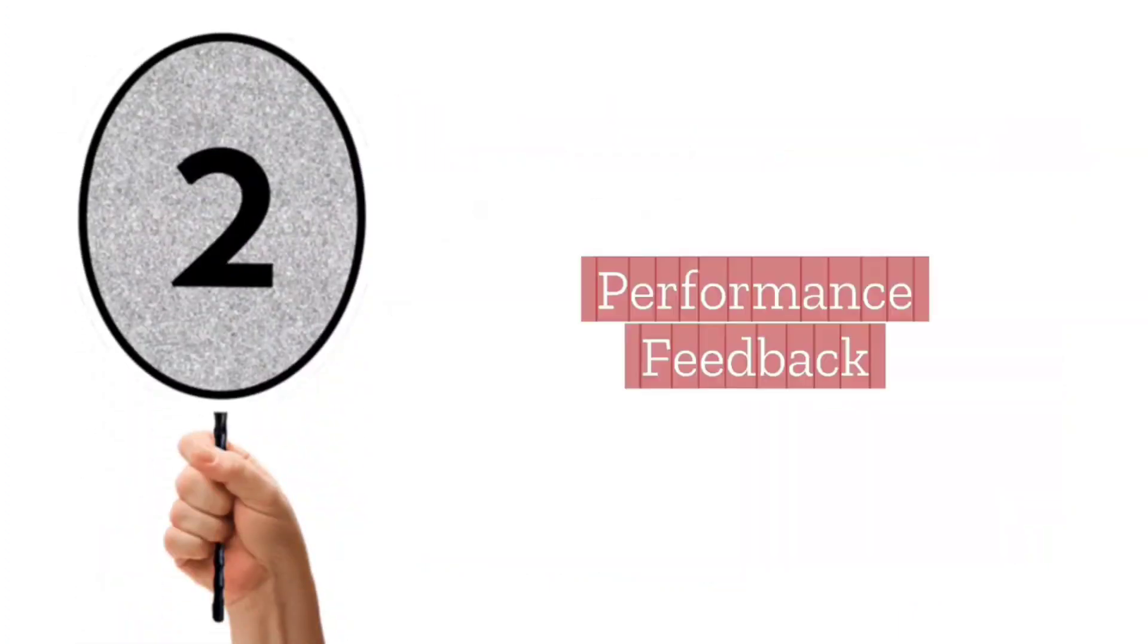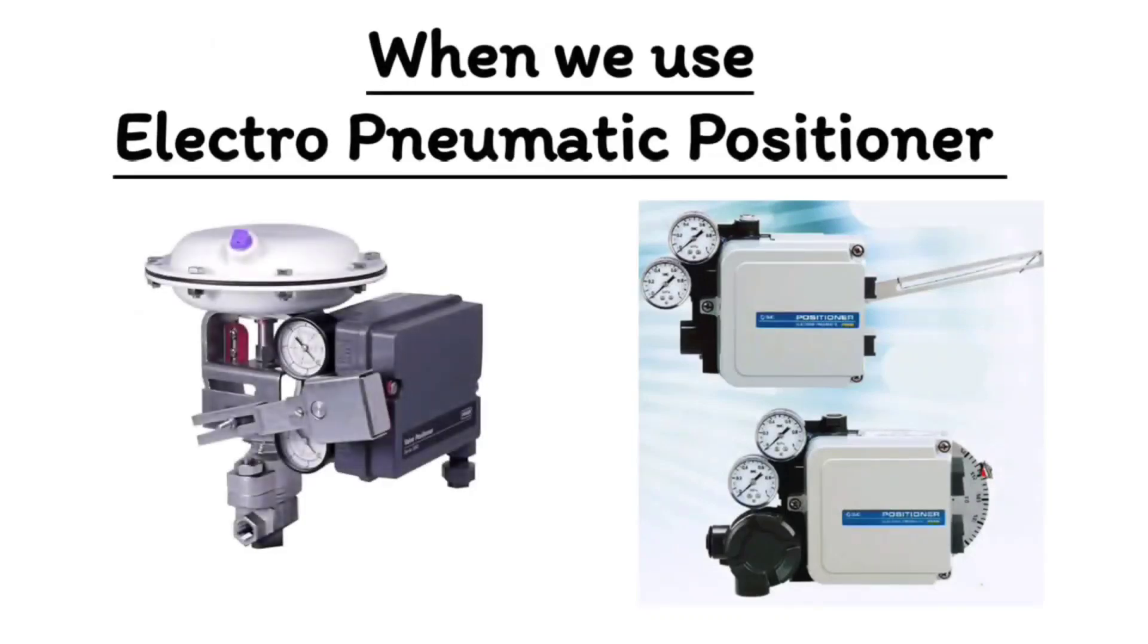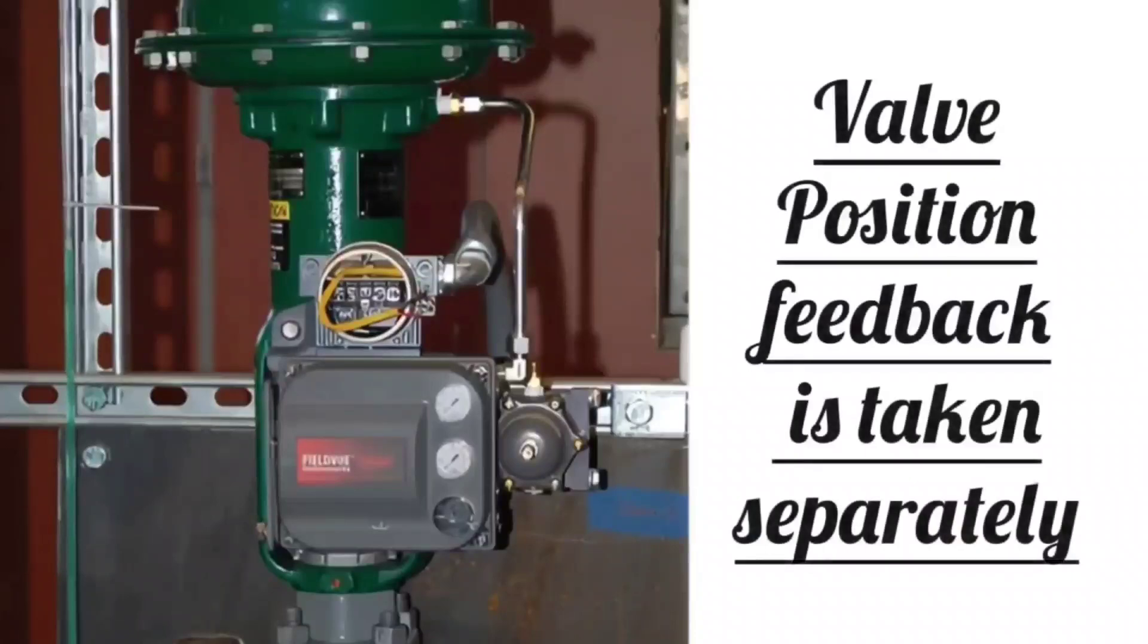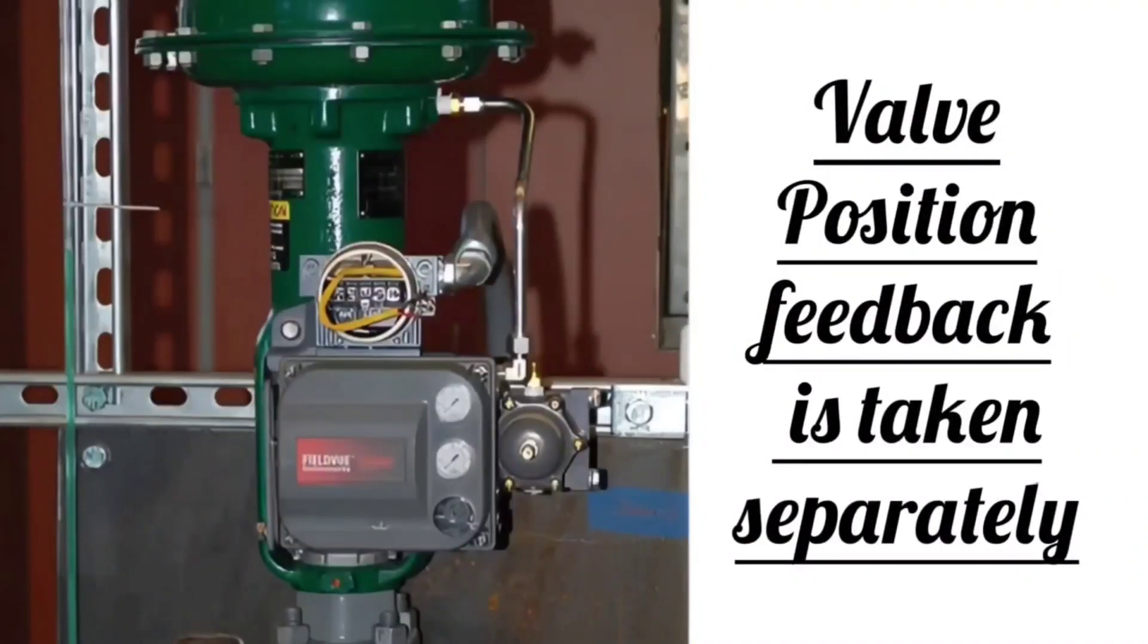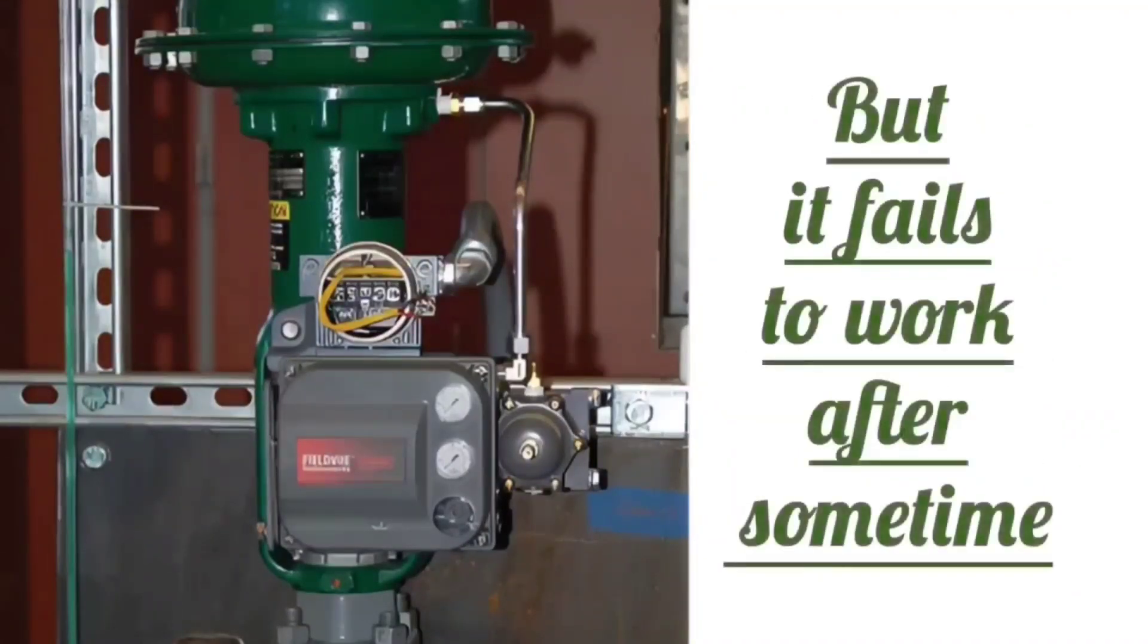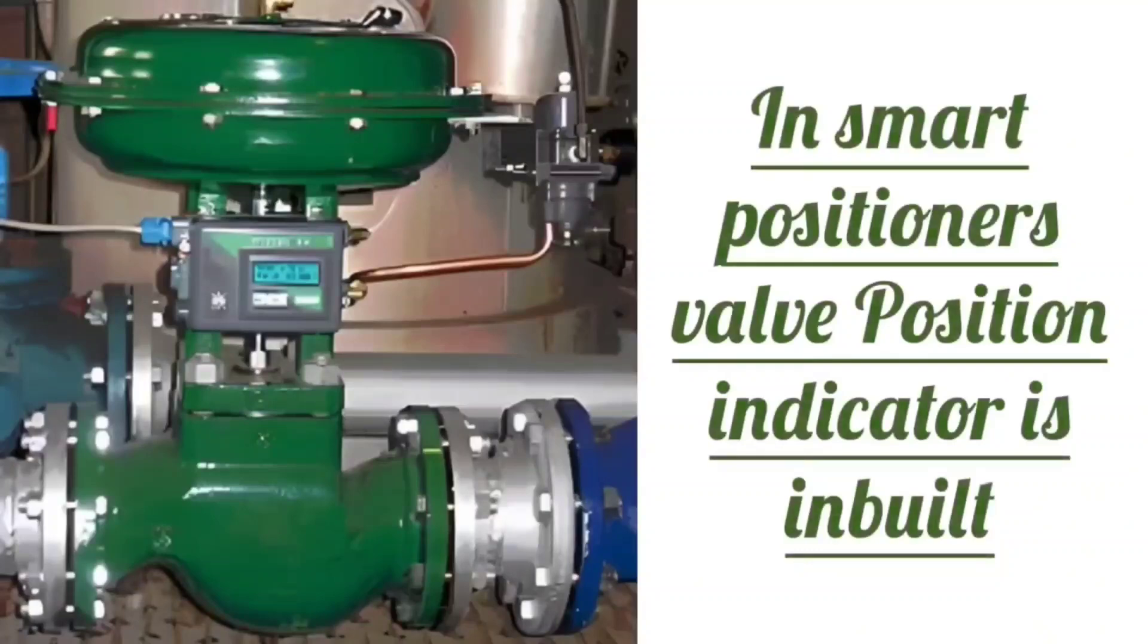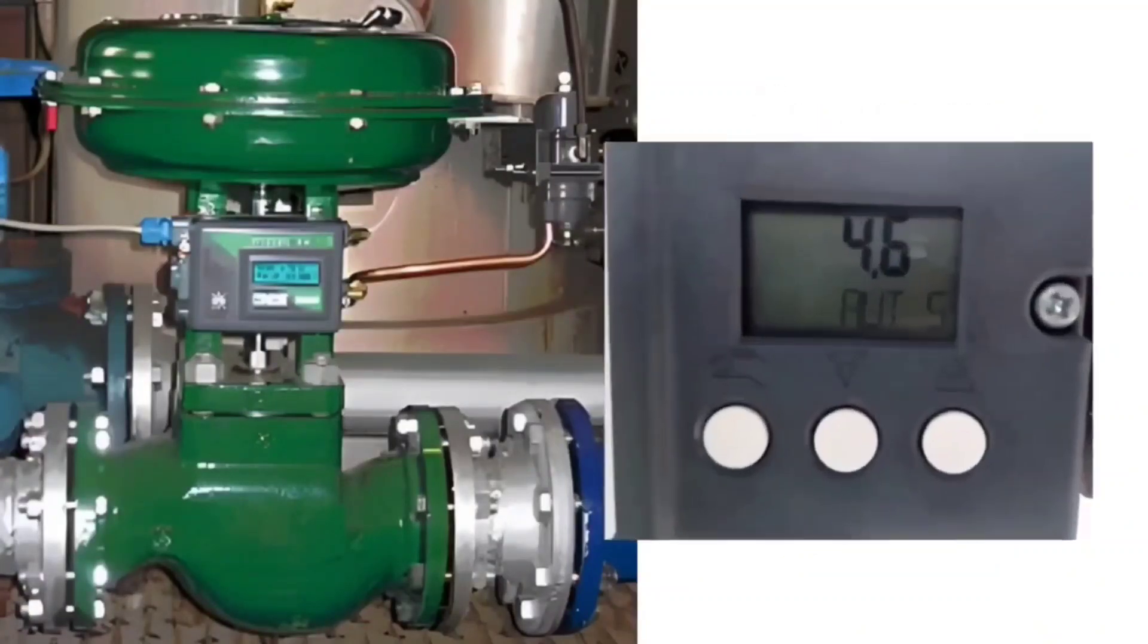Next is performance feedback. When we use normal electro-pneumatic positioner, the position feedback signal of valve has to be taken separately, which normally fails after some time. So valve's opening percentage has to be seen in the field. Smart positioner has inbuilt valve position indicator and you also get the feedback of the position of the valve.